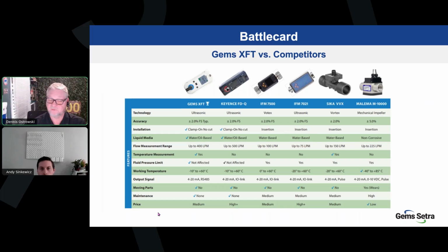Fluid pressure, obviously, if you're mounted inline in a pipe, pressure is going to be something that you've got to watch for. And obviously, with a clamp-on, no contact type of application here, you don't have to worry about that. The output signal 4 to 20, which is very common. No moving parts. And as you see across the board here, the XFT comes out on top in many of these categories. Okay, next slide.